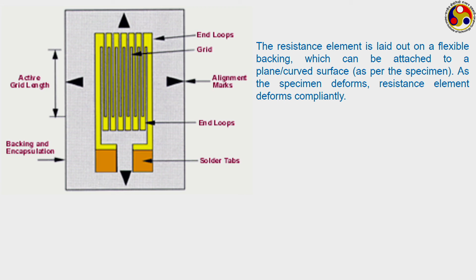And how do we get an idea about the change in the resistance? We can easily go for a Wheatstone bridge combination like this, where the strain gauge forms one arm of the 4 resistors. In the normal scenario, when the gauge is not under any kind of strain, this voltmeter will read a 0 value, but whenever some kind of stress is put onto this, the voltage value will change. We shall be getting a non-zero voltage value, and that can directly be calibrated to the deflection.